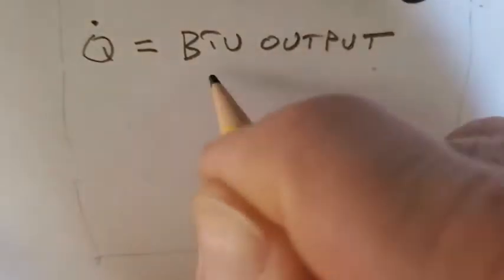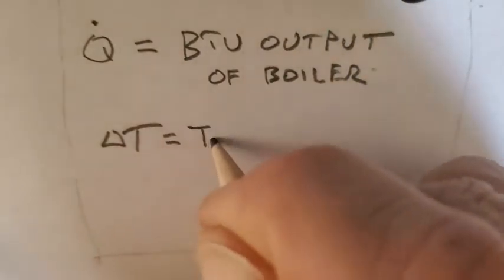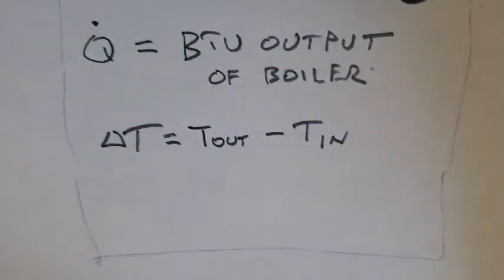So if we know the boiler output at high fire or low fire, it doesn't really matter. And we know our delta T by using an infrared, measuring the inlet and outlet, subtracting the two.